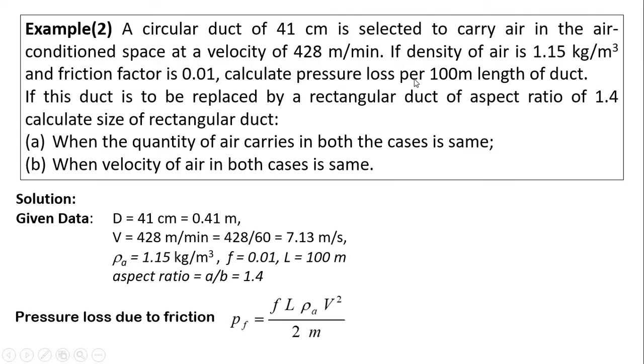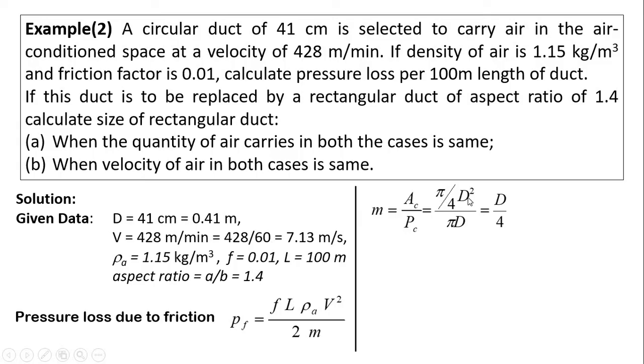For pressure loss due to friction, all values in the formula are known except hydraulic mean depth M. For a circular duct, M = cross-sectional area divided by wetted perimeter = (π/4·d²)/(π·d), which simplifies to M = d/4. With d = 0.41 m, hydraulic mean depth M = 0.41/4 = 0.1025 m.